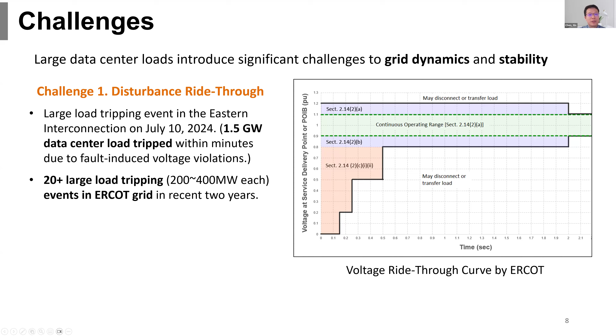Currently, ISOs and utilities want to impose requirements on the ride-through capabilities of large loads. For example, this is the voltage ride-through curve imposed by ERCOT, which means facilities need to follow this curve. Once there is a voltage sag or voltage increase from the grid, the data center facility cannot disconnect instantaneously, they need to stay connected for some time. For example, if the voltage drops to 0.7 per unit, the data center should stay there for at least 0.5 seconds. So this is the ride-through rule.